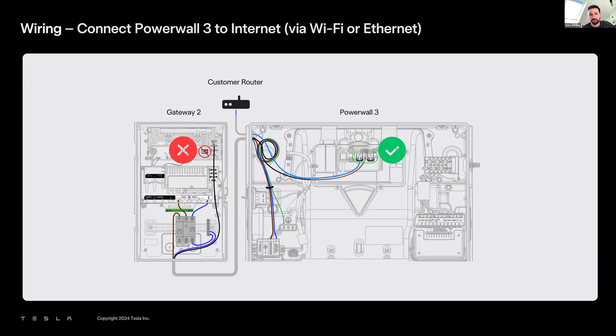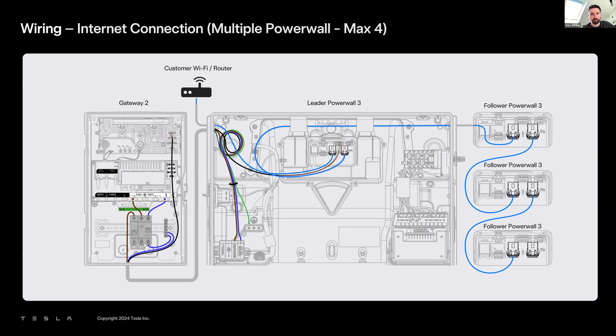If you're having multiple Powerwalls, the comms from unit to unit is much easier. You link communication from Powerwall to Powerwall through Ethernet, going port B to port A, B to A, B to A. It's just an Ethernet connection from one unit to the next for the comms. It's super straightforward, couldn't be any easier. We've made it as easy as we possibly can to connect the communications from multiple Powerwalls together.